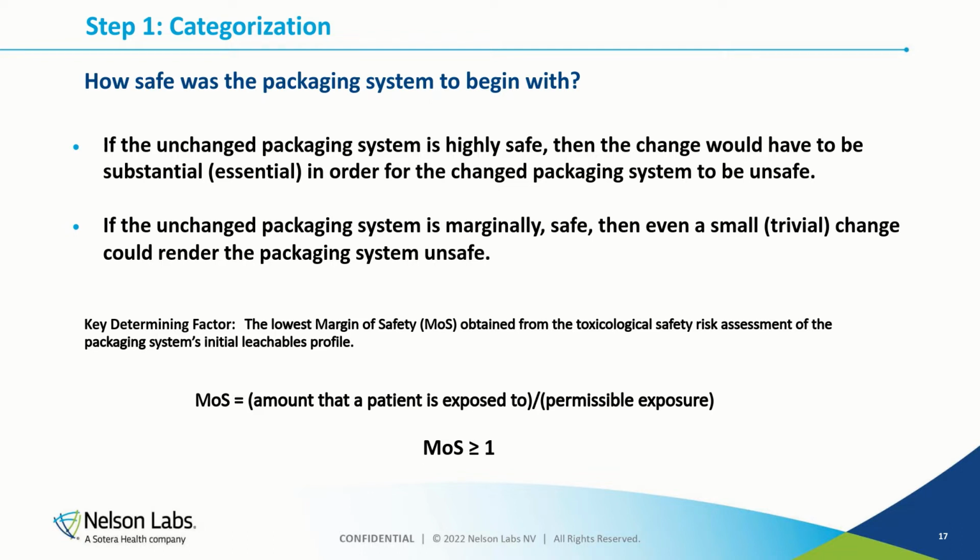And in that toxicological safety risk assessment, the concept of a margin of safety should play a very important role. And the margin of safety is exactly what it is described to be. For a leachable, the margin of safety is the ratio of the amount that the patient is exposed to versus the permissible exposure of the leachable.